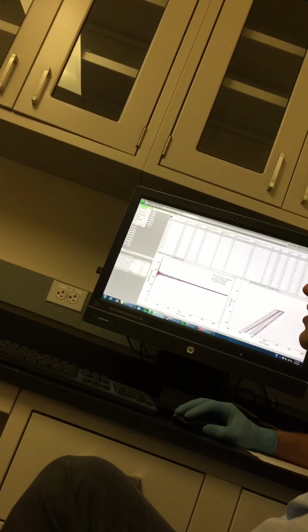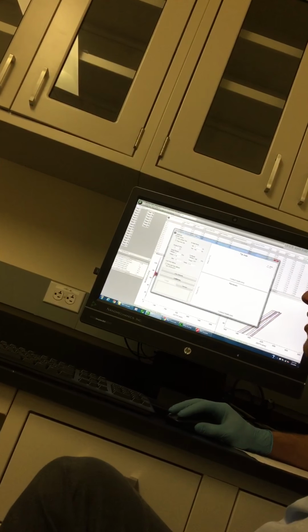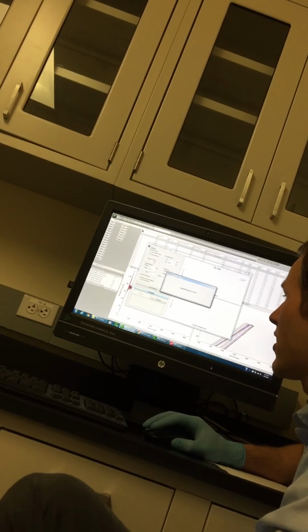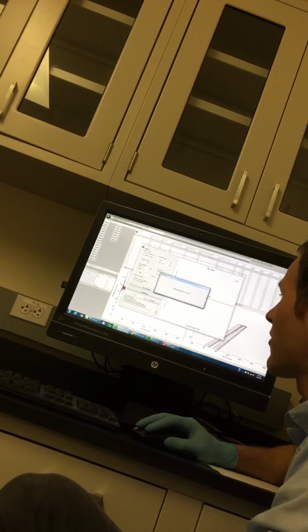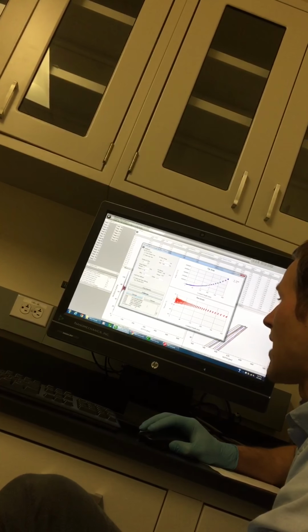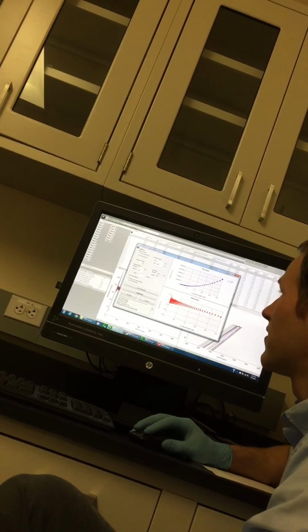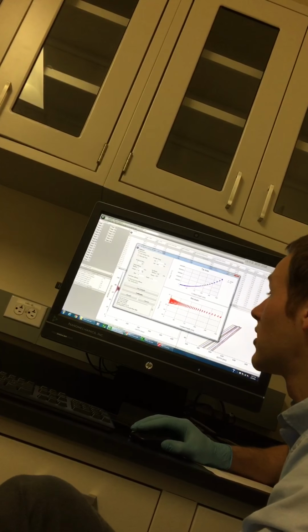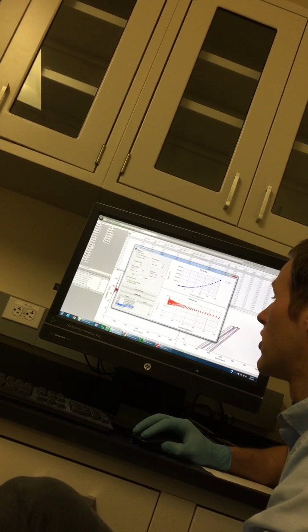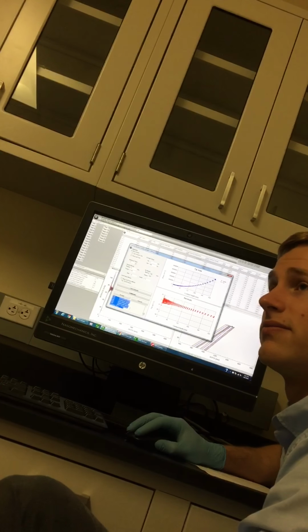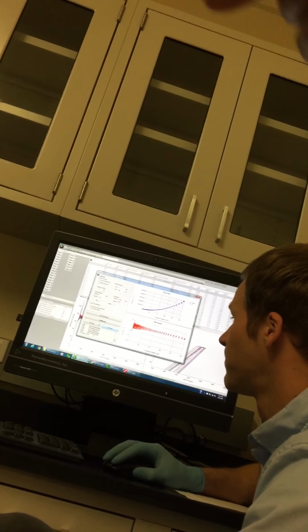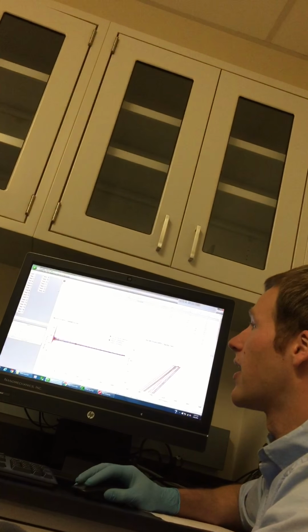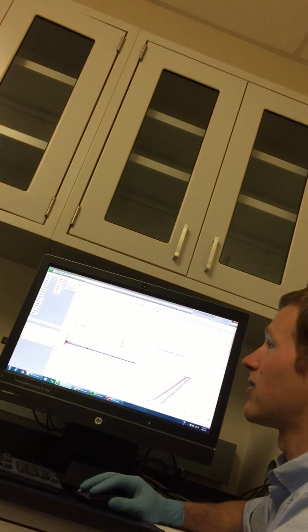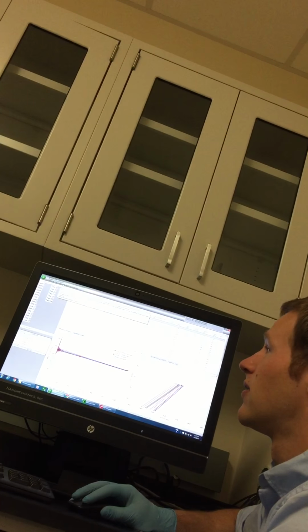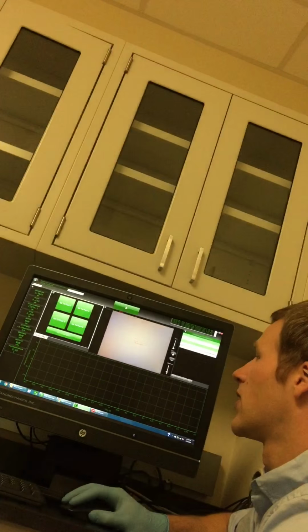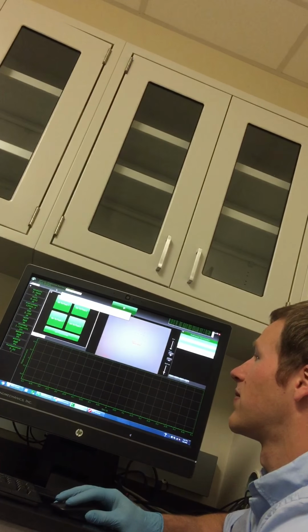So then to calibrate it, I would go to tip and settings, advanced tip calibration, and then hit calibrate. It's fitting on the data that we have up right now, and then I would hit accept, and it would change the values of this tip that I had selected or that I had just created. It would change them to whatever it found here. The tip, you mean the indenter tip? Yes. Okay. Yeah, and you can tell what tip you have selected or what it's going to do by looking right here. It says tip. And it also should show it here.